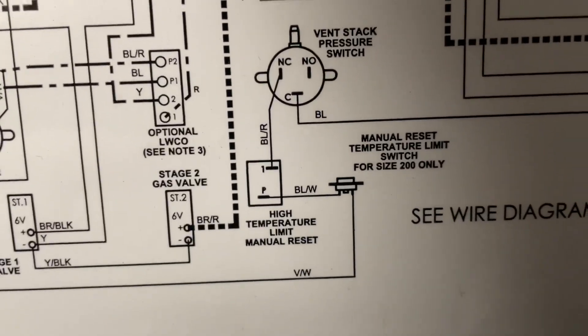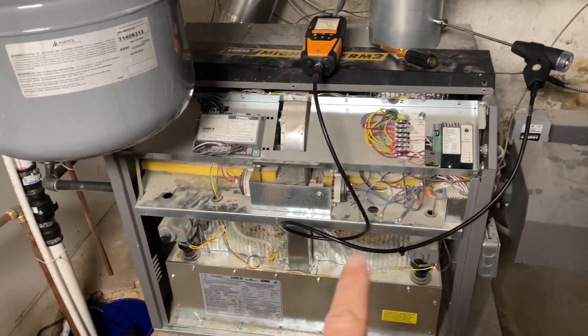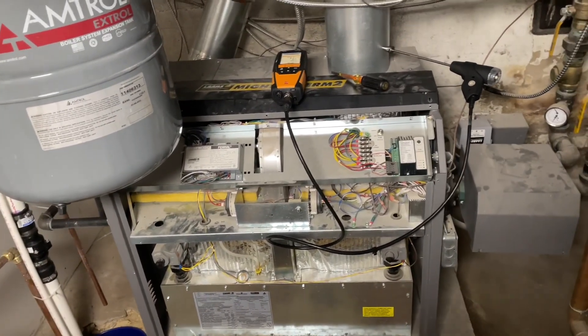When I got here today — they have no heat again on the main zone — the property manager just turns everything off. She turned this off, which was working fine, and turned this off. I noticed this little switch right here: this is called your manual reset high temperature limit. This thing will go off when there's too much temperature. So I pushed in that little button, kind of like the blocked vent switch — the spill switch on a boiler.